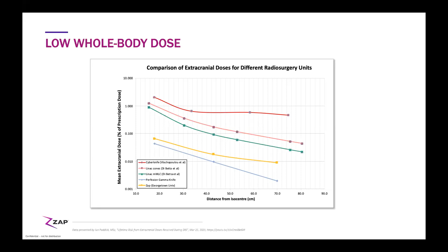Meanwhile, because of the extensive shielding that goes in the ZAP-X, it really delivers minimal dose to the rest of the body. And you'll see this set of curves measures different types of radiosurgical devices, from CyberKnives to linear accelerators to the Gamma Knife Perfexion. And the Gamma Knife Perfexion still does deliver the least whole body dose of radiation, but very closely following it is the ZAP-X. And the other devices deliver as much as 2 orders of magnitude more radiation to the rest of the body. Now, I think this is going to be of particular importance as we think about treating children. And that's something that increasingly we have more and more experience with in using the ZAP-X.